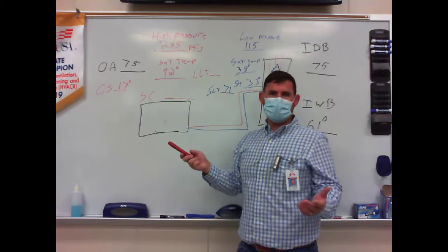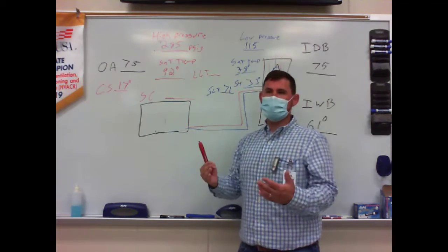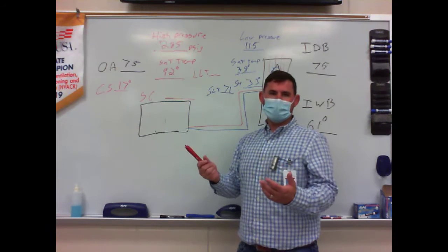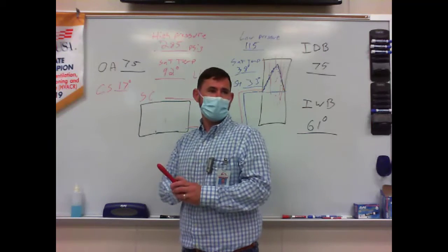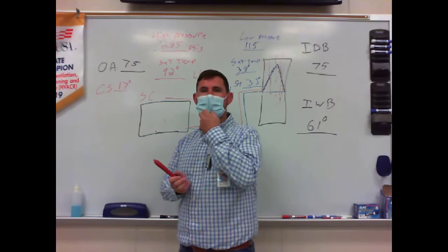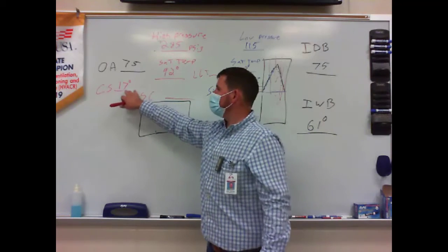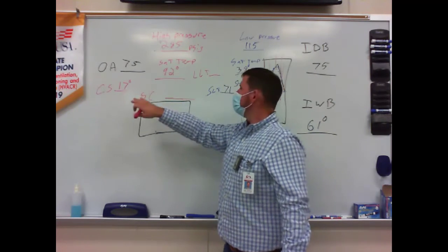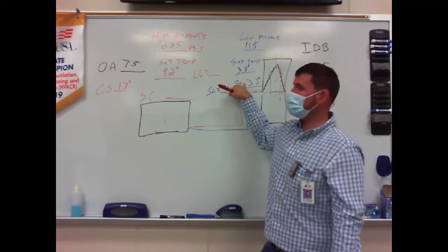What do we think? It's a little bit on the low side. It's not terrible. If it's a high efficiency piece of equipment, that wouldn't be bad. Yours actually is a high efficiency piece of equipment, isn't it? I think y'all have a 17 SEER 2-stage Trane. So it's really not bad. I'm okay with that. That's a little low. That tells me that we're starved.